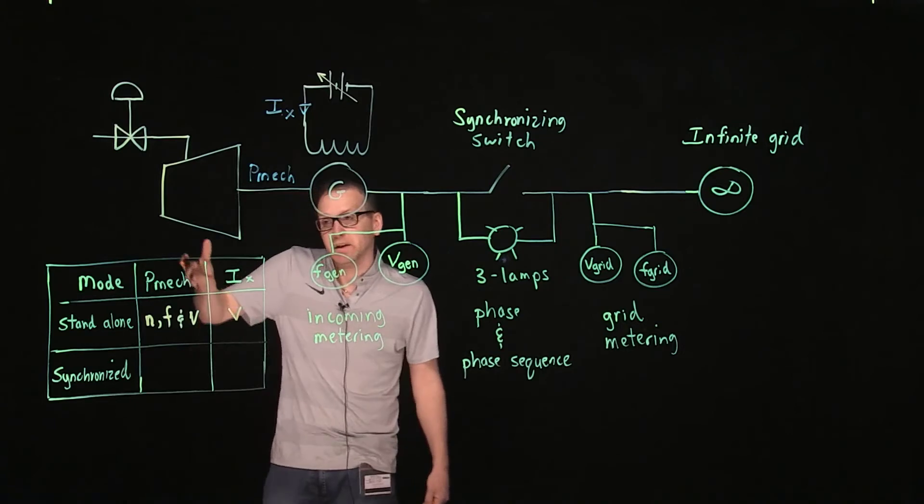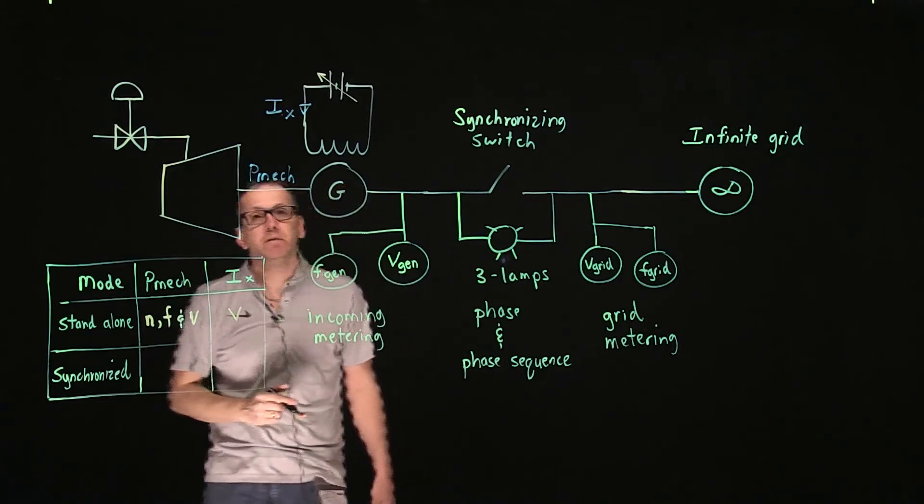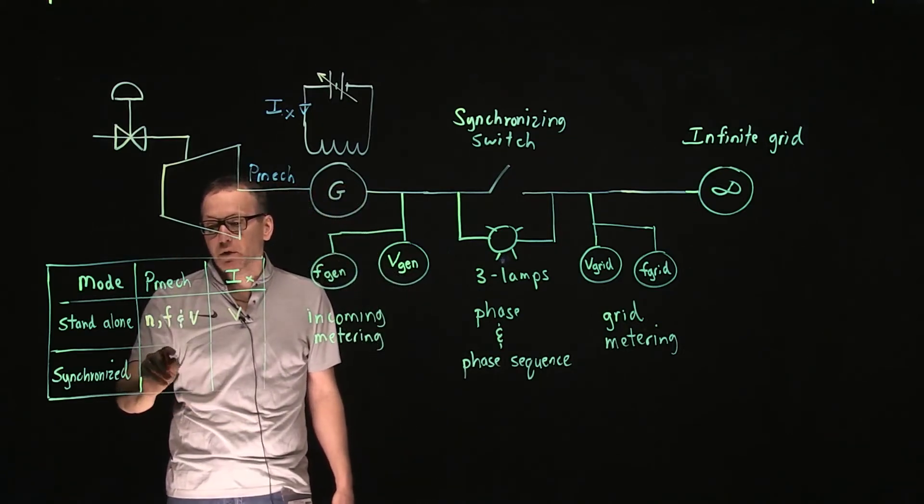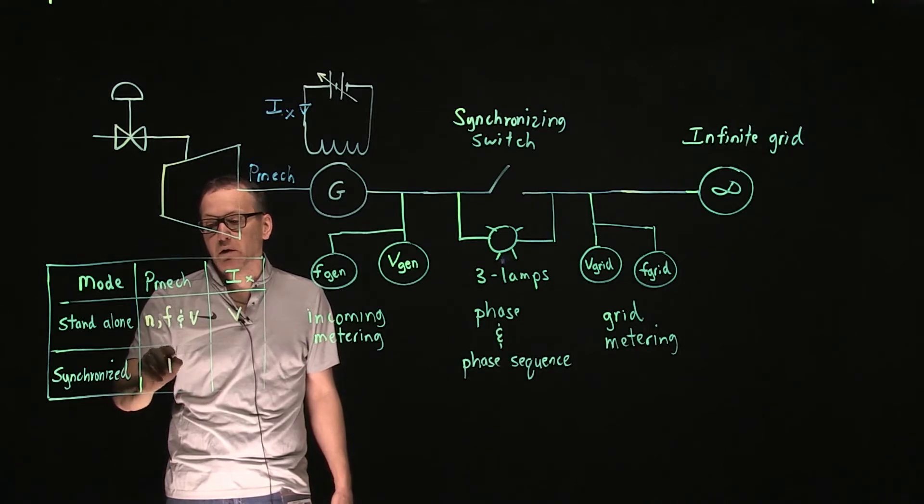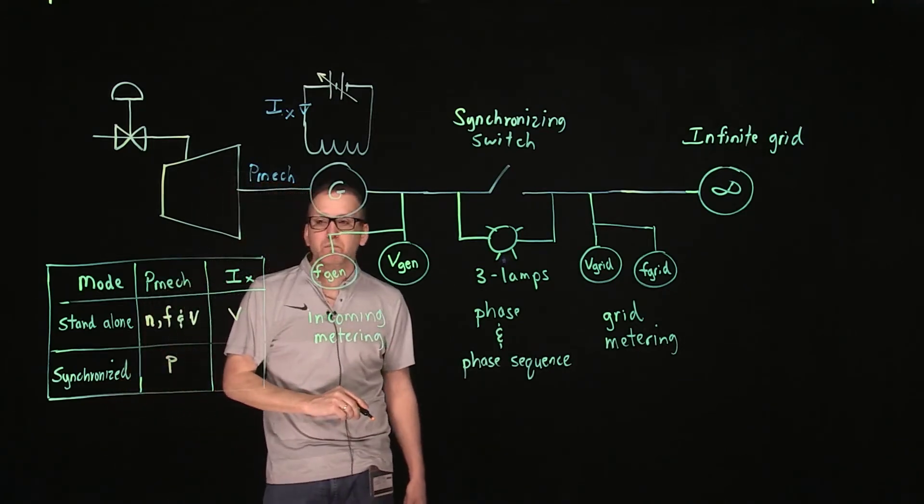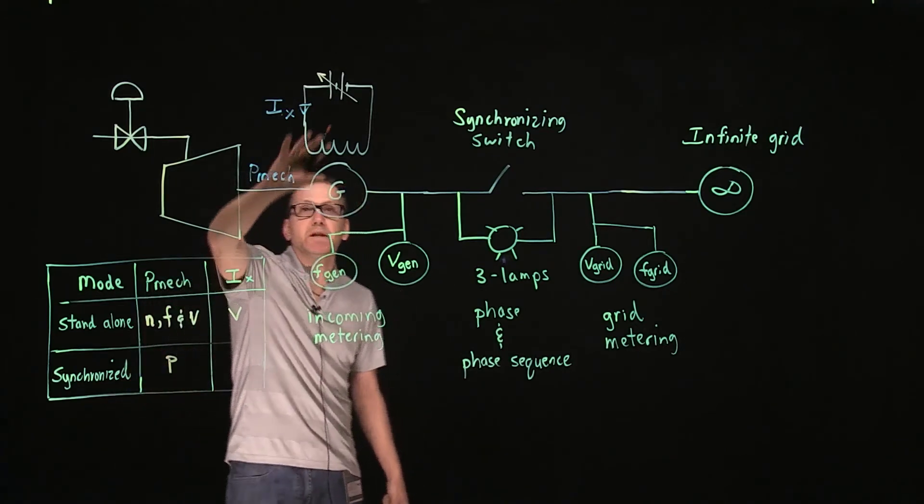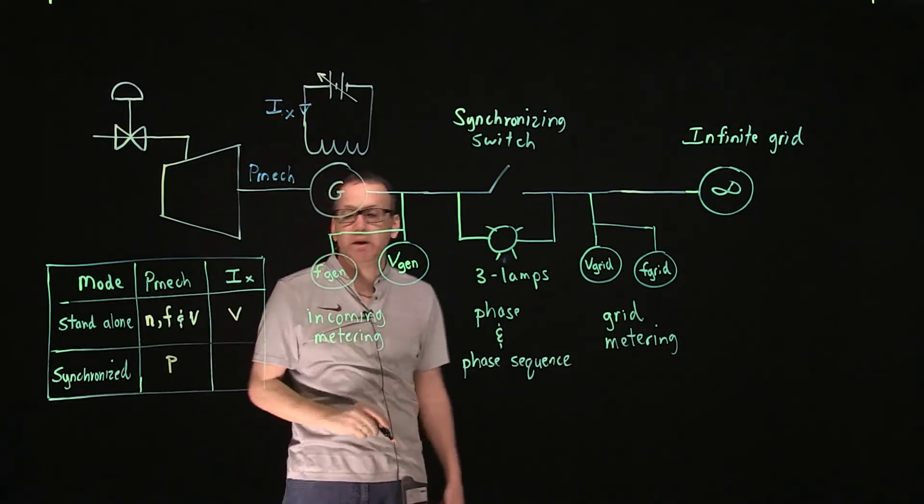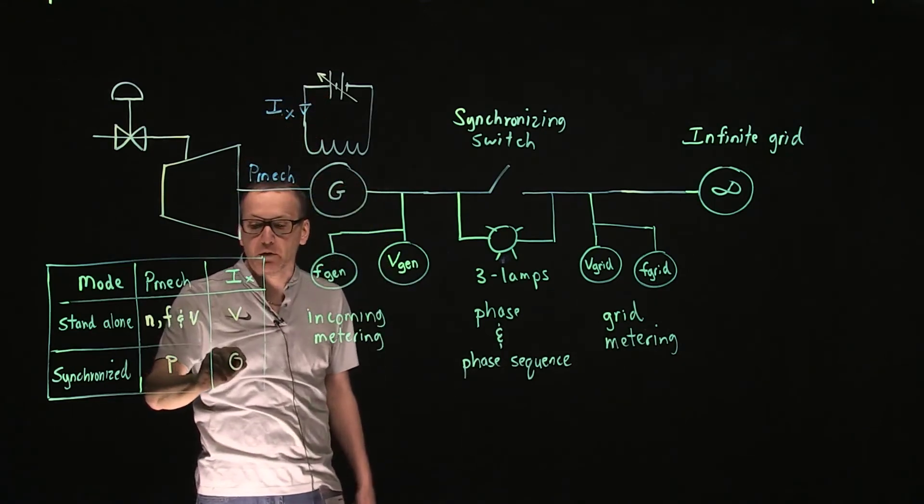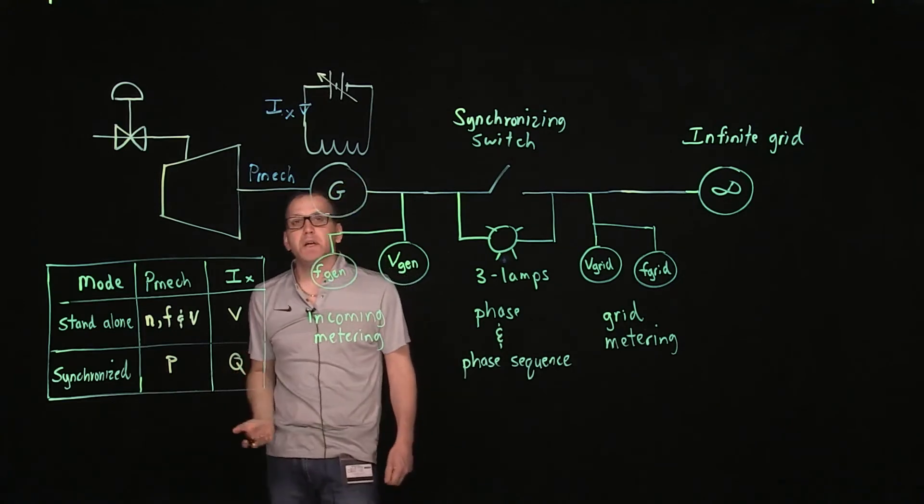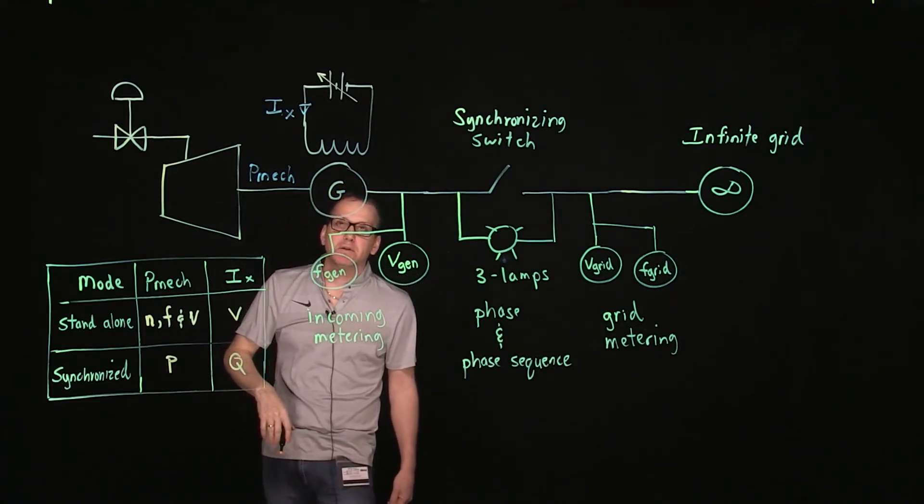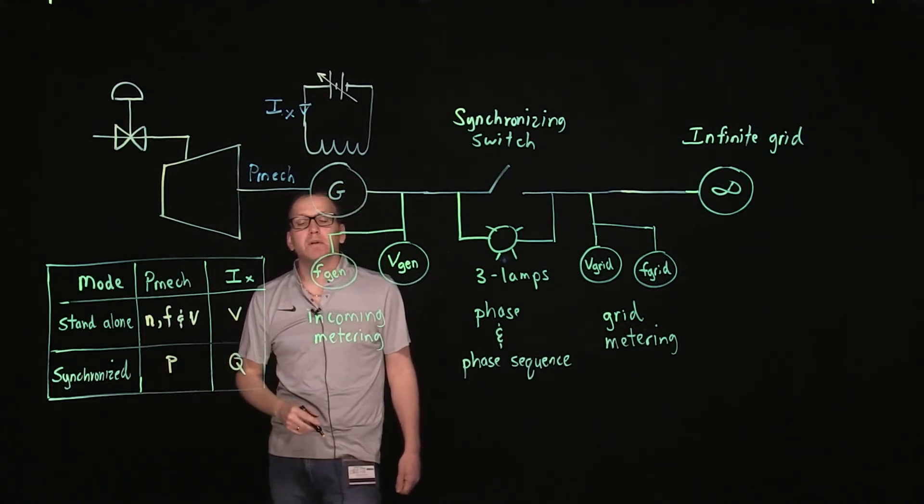When we're operating in synchronized mode and we adjust the mechanical power input to the generator, the only thing we can adjust is the real power or the P. By adjusting the excitation, the only thing we adjust is the reactive power or the Q. We can over-excite or under-excite the machine to import or export reactive power, and we can also import or export real power.